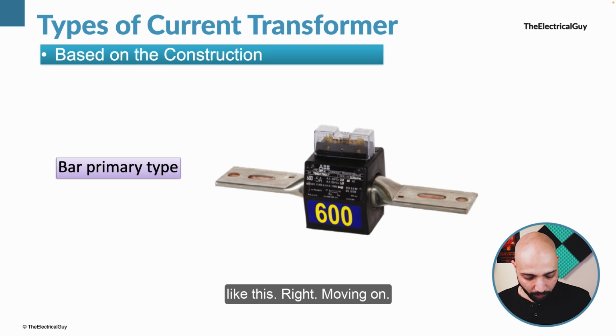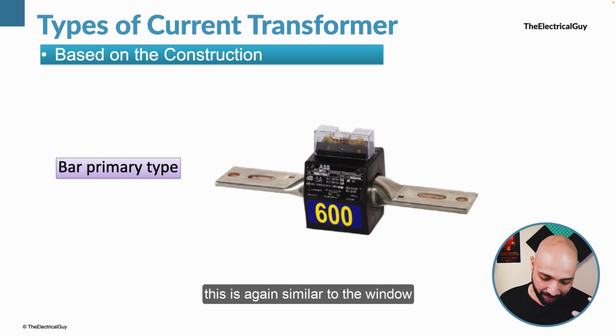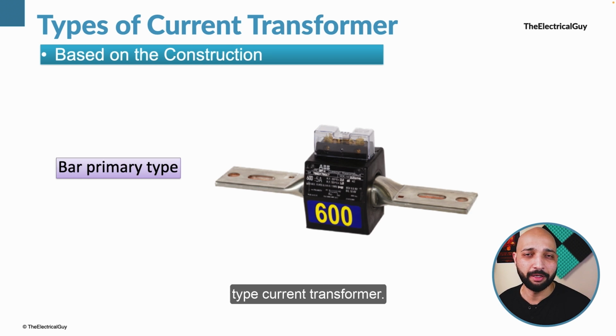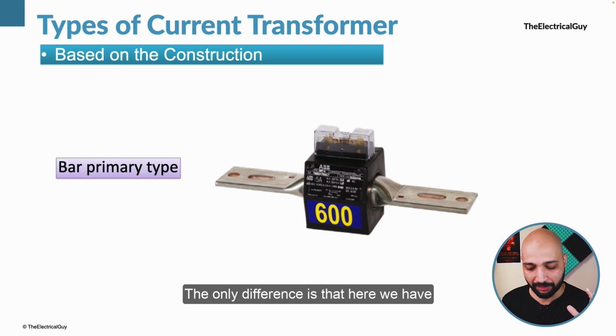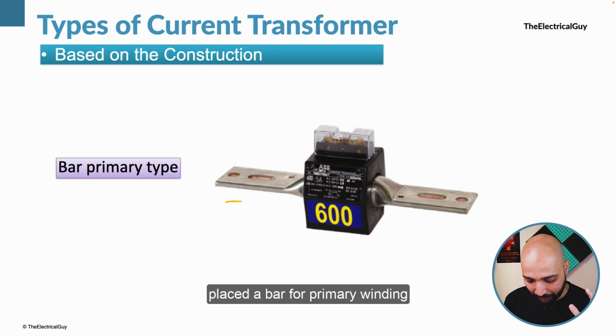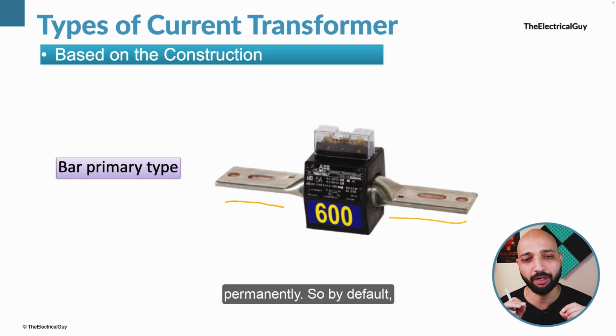Moving on, we have a bar primary type current transformer. Now this is again similar to the window type current transformer. The only difference is that here we have placed a bar for the primary winding permanently. So by default, it will come with this.